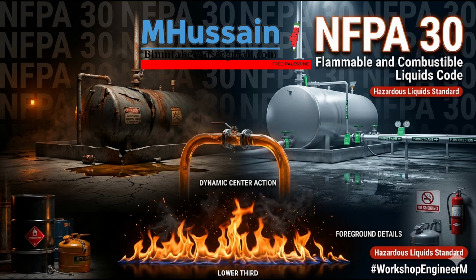Right. Let's start with the absolute scariest end of the spectrum. Class I liquids. These are liquids with a closed cup flash point below 100 degrees Fahrenheit, or about 37.8 Celsius. And I'd argue that 100-degree Fahrenheit mark is the most critical dividing line in the entire code. Really? Why 100 degrees? Because it represents a standard, achievable ambient temperature. If a liquid flashes below 100 degrees, it means that on a warm summer day, just sitting there in its natural environment, it has enough thermal energy to generate a highly explosive vapor layer. You don't even need a heater or a fire. The weather is enough. Exactly. The weather does the work for you.